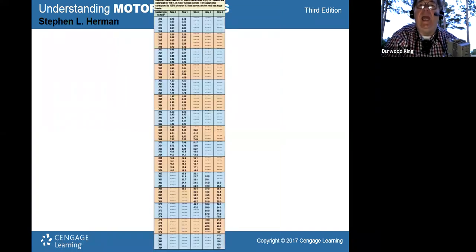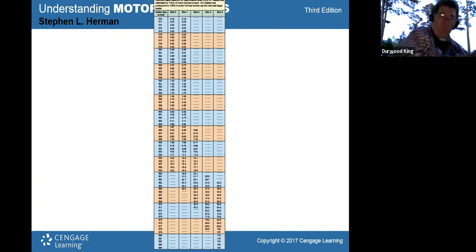All right. And then overload sizes. Let's see if I can get a light on. I actually need to get a light on out here. Hold on one second. Well, you can actually see me still pretty good, can't you? Yes, sir. Right. I'll get a light to put on the motor here in just a minute. We're getting ready to show you how to test a good and bad motor. What that chart is there, that chart is for separate overloads that are not adjustable, overloads that bolt into a starter, that are fixed overloads.